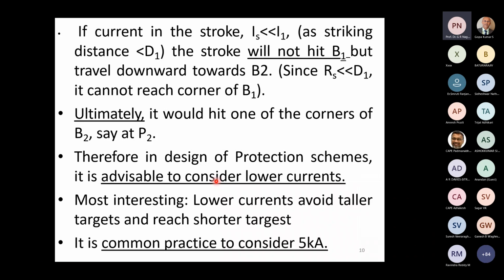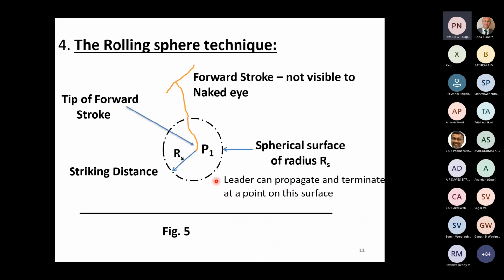Now, the important conclusion one can draw is that if we design a system for 5 kiloamperes, the lowest current, then it's safe for all the other currents also, because a lower current stroke can always play a trick, avoid the tallest object, and come and hit the shorter objects. Therefore, if we design the system for 5 kiloamperes, then we have designed it also for the higher currents. Okay, now let's go further.